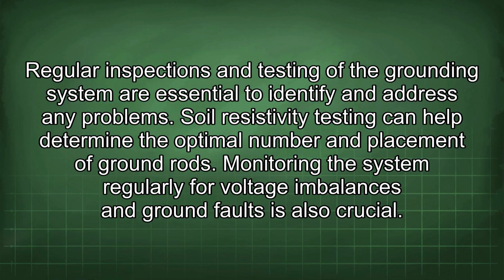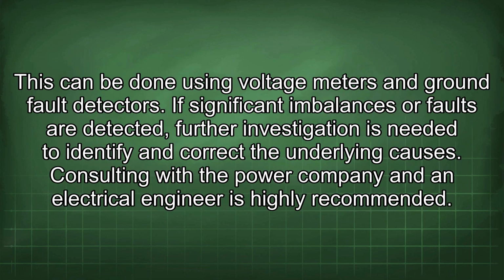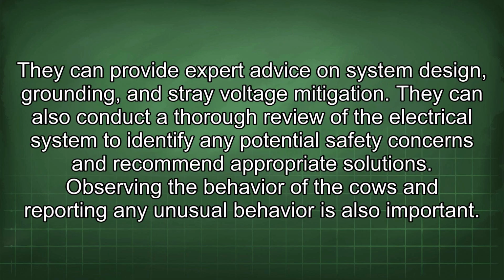Monitoring the system regularly for voltage imbalances and ground faults is also crucial. This can be done using voltage meters and ground fault detectors. If significant imbalances or faults are detected, further investigation is needed to identify and correct the underlying causes. Consulting with a power company and an electrical engineer is highly recommended. They can provide expert advice on system design, grounding, and stray voltage mitigation.